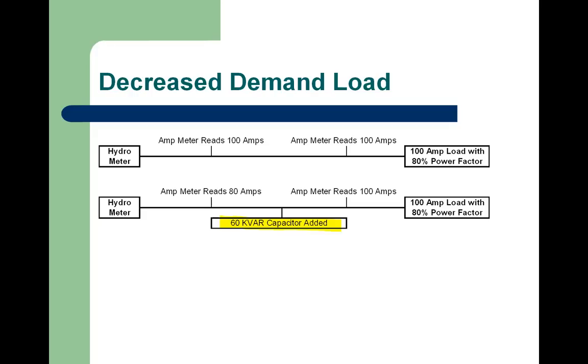However, if we take a 100 amp load, and this could be one large motor or a number of different pieces of equipment, and we put a simple amp meter down by the motor, it would read about 100 amps. And if we took one up by the hydro meter, it would be about 100 amps. If we equate 100 amps at 600 volts to be approximately 100 kVA, it's a fairly close number.